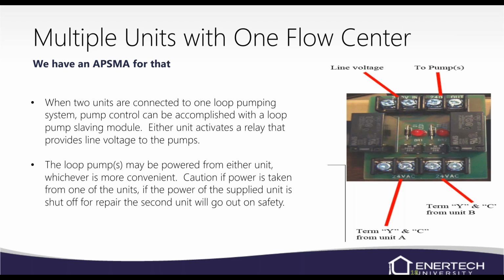So basically, when two units are connected to one loop flow center, you can see you've got Y and C from unit A on the right there, and Y and C from unit B. And then you're going to have your line voltage coming in from one of the units. So that's 208, 230 volt from one of the units to power that control all the time, the high voltage. And then those relays, if one of those units is calling, will close and send the power to the pump on the flow center. So if either one is calling, the flow center runs.